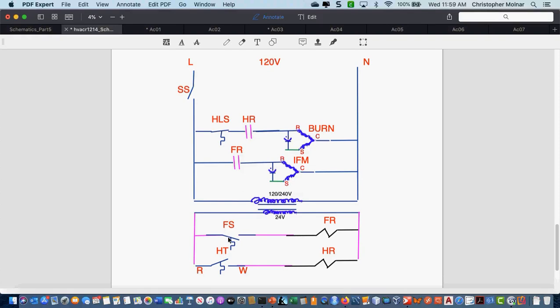I could have the fan switch, instead of on temperature, I could have it on time, using a time delay relay. More and more, and the reason I drew this down here originally for you guys, is that more and more, this is not temperature driven. It's based on time. The furnace fires, comes on, and W feeds a time delay relay. Waits 90 seconds before it energizes the blower motor. Okay? After the furnace shuts off, that time delay relay waits another 2 minutes, continues to run the fan to get the furnace cool.